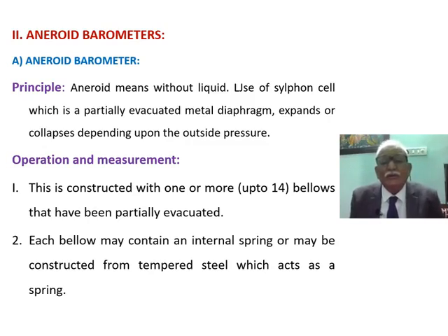So it uses a cell, which is a partially evacuated metal diaphragm. Not exactly zero pressure, but partially evacuated. The diaphragm expands or collapses depending upon the pressure.